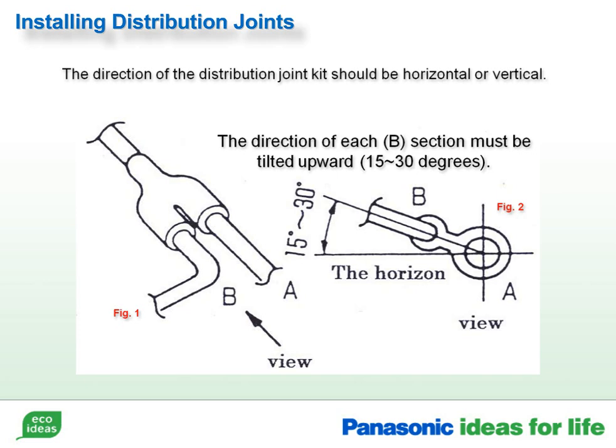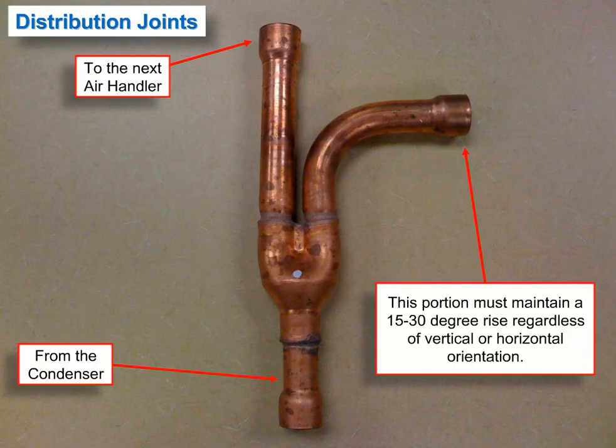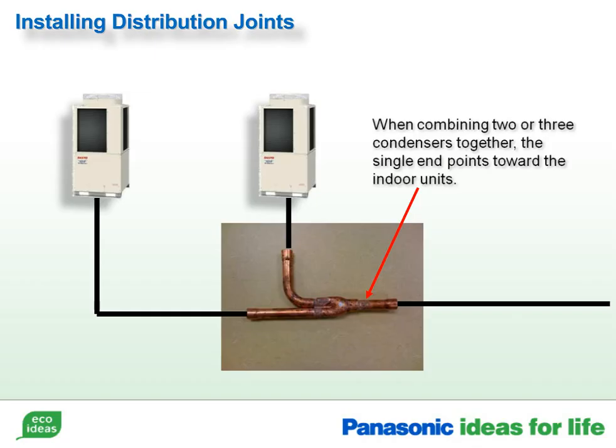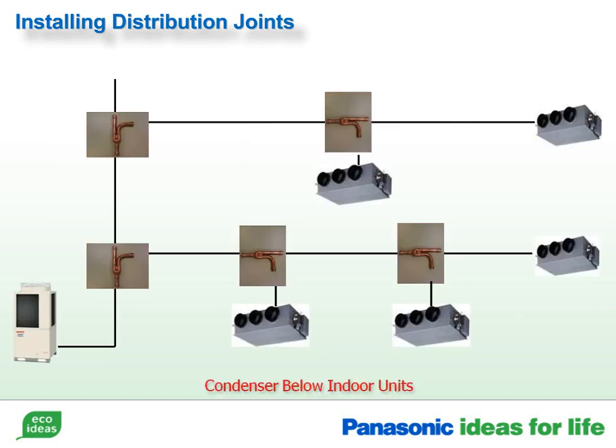If the air handler is installed above the distribution joint, the tilt is not necessary because the oil will naturally return back to the condenser. All ECOi units have an oil recovery cycle, but proper piping pitch will keep this feature from occurring too frequently, and increase system efficiency. The single end of the distribution joint should always point towards the condenser. There is only one exception to this rule. When there are multiple condensers piped together, the single end of the distribution joint should always point towards the indoor units. This example shows an installation with the condenser below the indoor units.